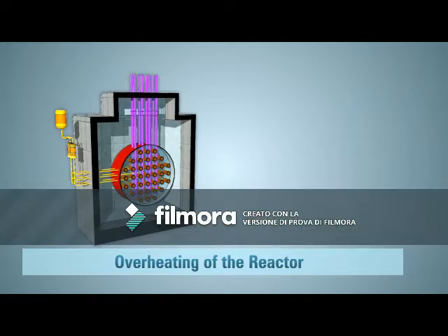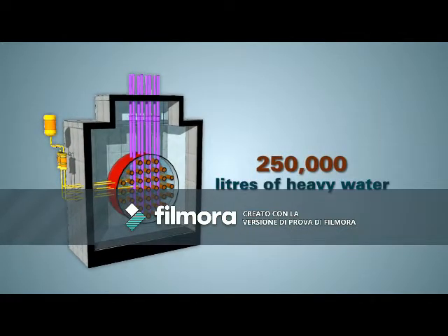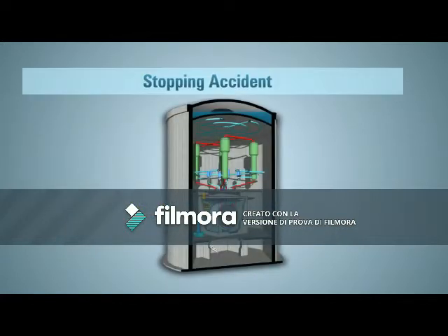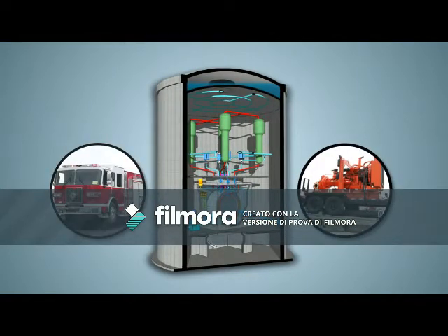If nothing is done at this point, the 250,000 liters of heavy water inside the calandria starts to heat up. The calandria is what holds the fuel. Supplying water to the calandria using emergency equipment such as fire trucks would stop the accident.